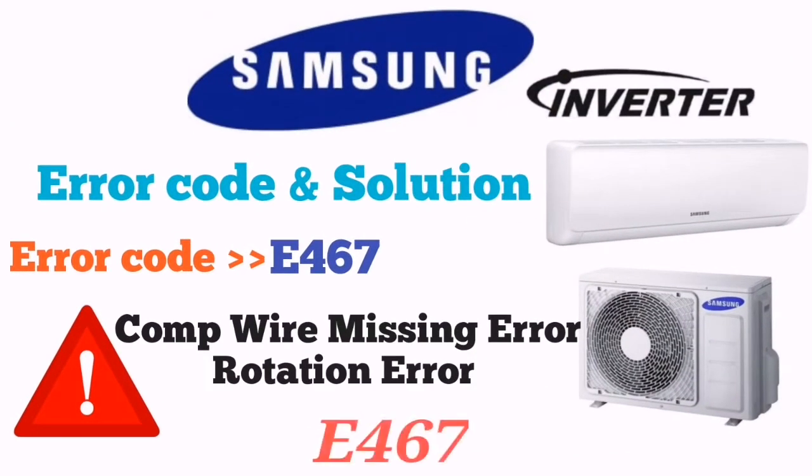When you see error E467, or your LED 1 and LED 3 are on and LED 2 is blinking, it means compressor wiring miss error or rotation error. To sort out this issue E467, you have to see the error E461 and follow the process, and you can solve the troubleshooting and your unit will be working.